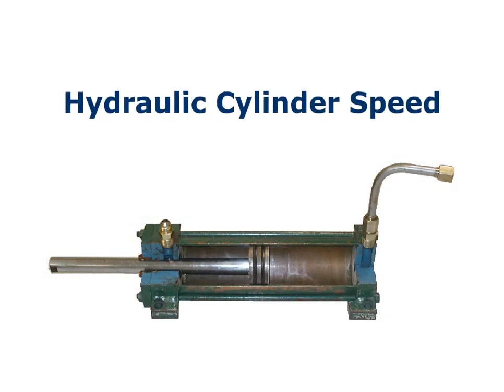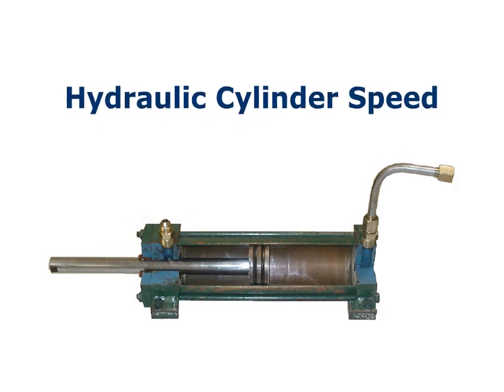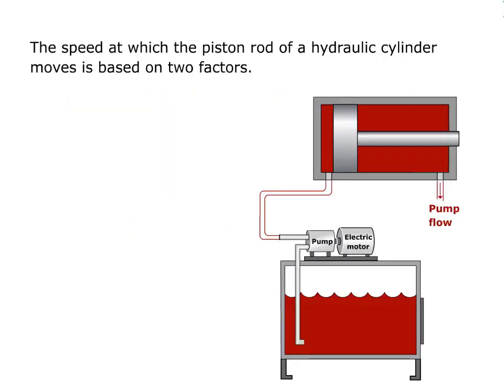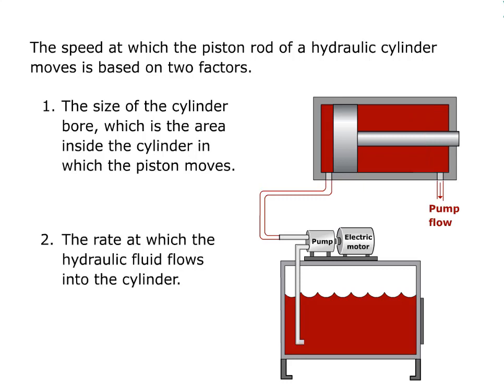Welcome to the video Hydraulic Cylinder Speed. The speed at which the piston rod of a hydraulic cylinder moves is based on two factors: first, the size of the cylinder bore, which is the area inside the cylinder in which the piston moves, and second, the rate at which the hydraulic fluid flows into the cylinder.